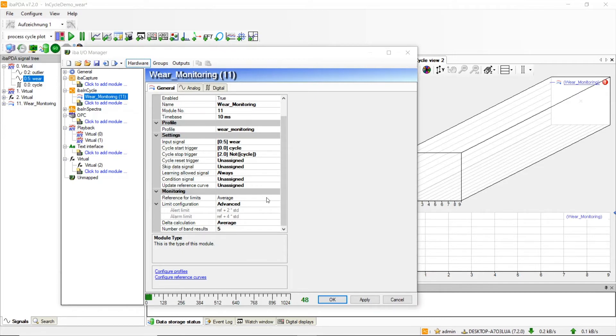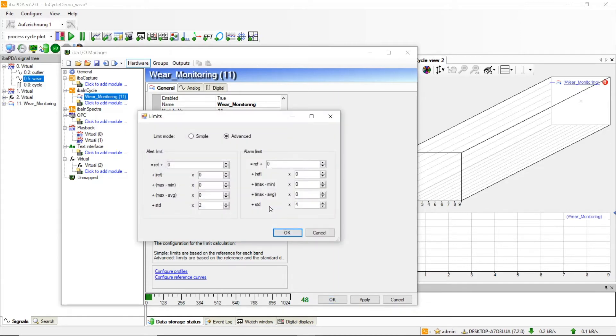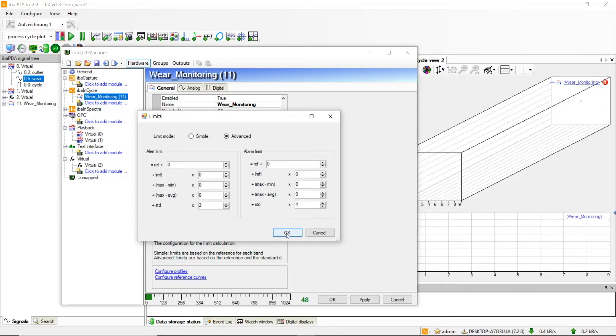We choose advanced limits which also takes standard deviation into account as a limit in addition to the learned reference curve. Here we select two times the standard deviation additionally to the reference as an alert limit, and reference plus four times the standard deviation as an alarm limit.